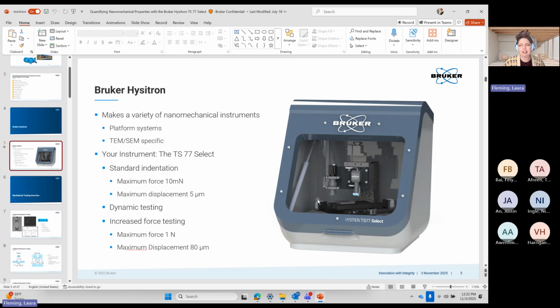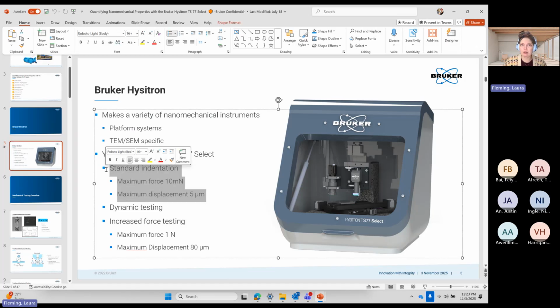So, a quick introduction to the TS-77 Hysitron Select. Bruker Hysitron itself, we make a lot of nanomechanical instruments. We make both platform systems, meaning ones that stand on their own, like yours, and then we also make models that go into TEMs and SEMs. Your system is capable of doing standard indentation, dynamic testing, and increased force testing. I believe that you only have a singular transducer that is a 2D lateral transducer. Does that sound correct? I think so. Okay, I'm like 99% sure on that, but I didn't have the document pulled up in front of me. So you can ignore this, but basically you have standard indentation and you are also able to do what we call scratch testing.